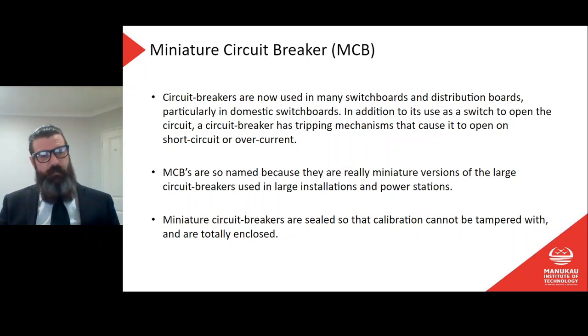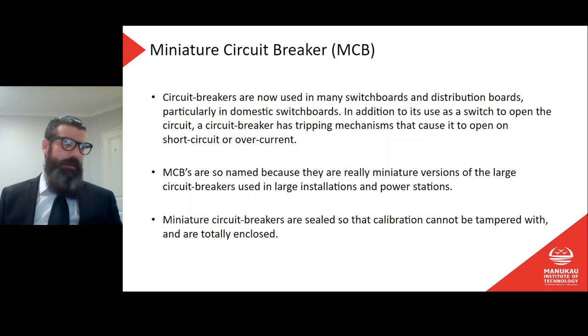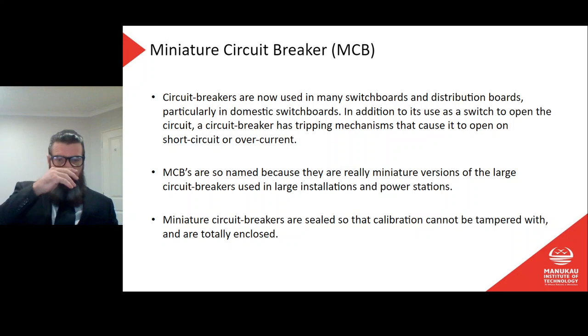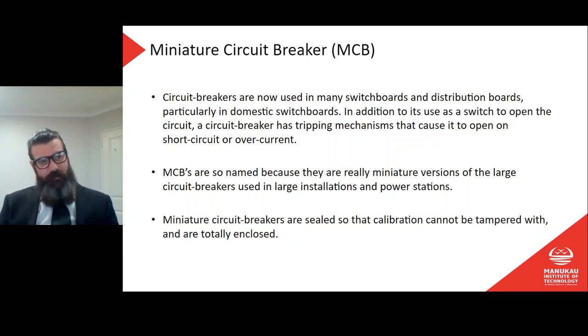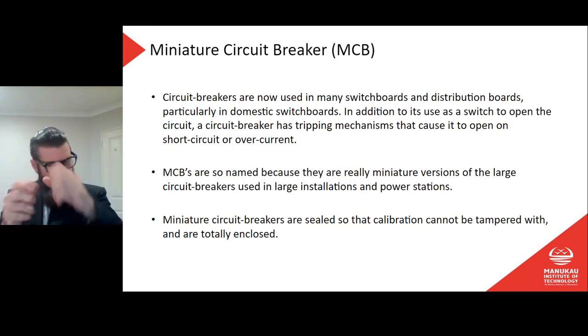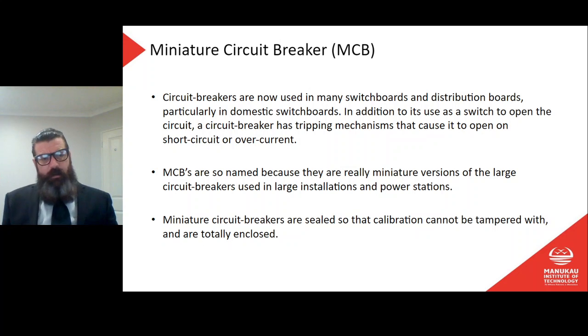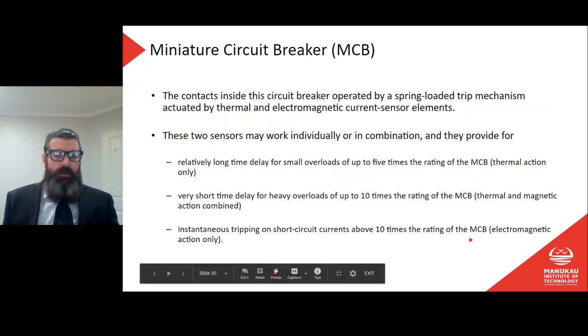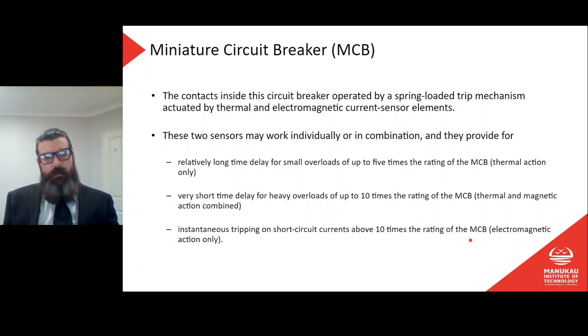With an HRC fuse, I need to physically pull that fuse out, which is fine, but then the question is, well, how do I prevent somebody putting something back in there? Not that people should, but we have to assume when we're isolating something that the dummy is going to come along and try and turn it back on. So what do you do with that? That's the question. With an MCB, we don't have that problem. We put a little lock over it, that little locking screw down mechanism, put our lock in, and no one can turn that back on. Great. They're really great for the vast majority of things in terms of protection.